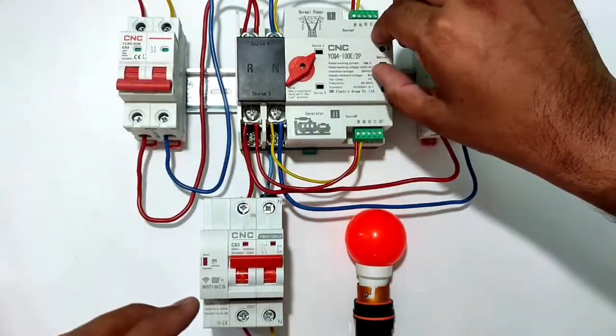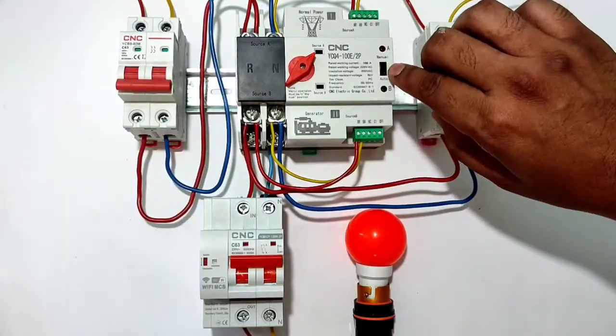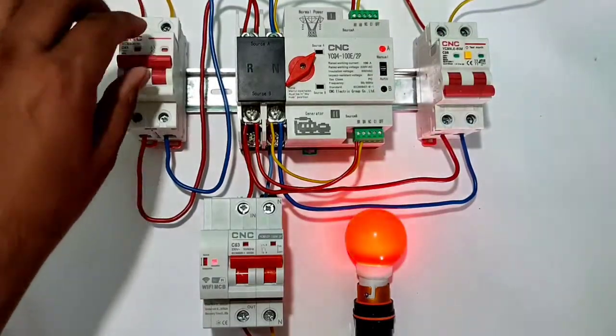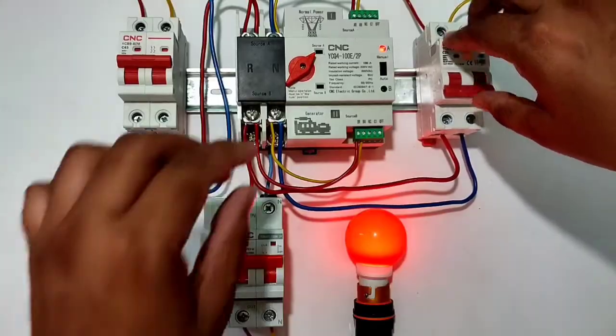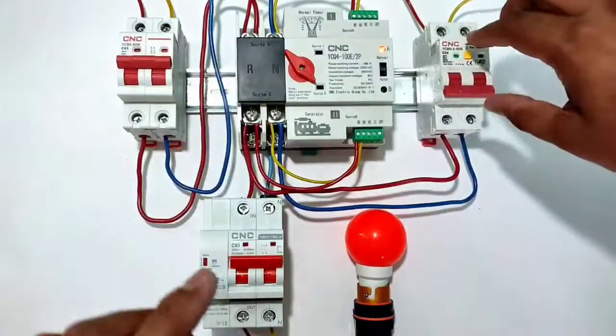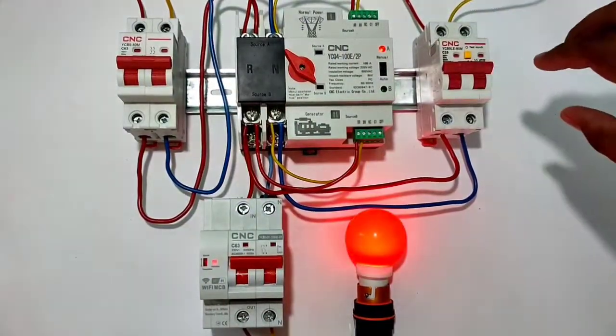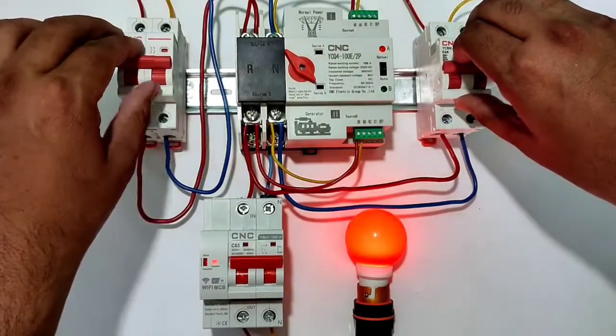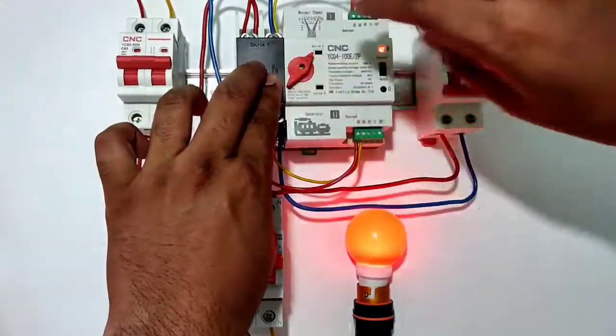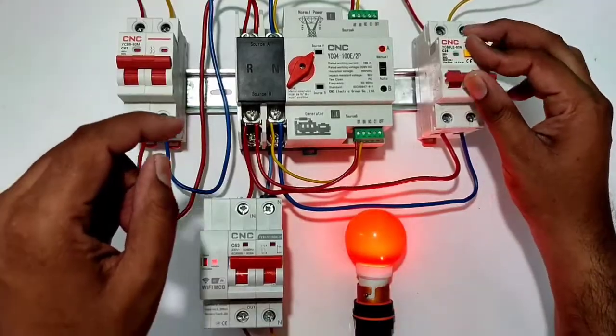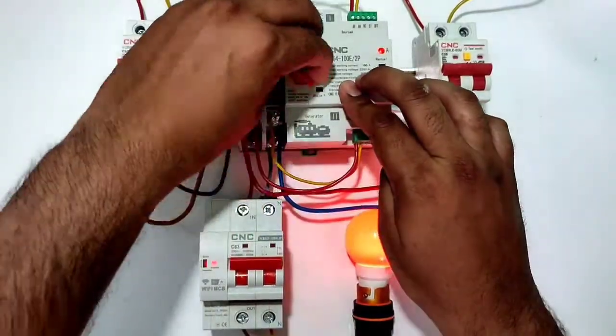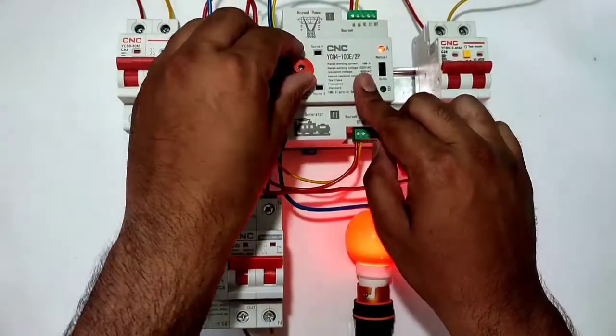It is simple. Now we select manual mode here, manually. Okay, we select manual mode. If you want to run your load on the main power supply, you can select it manually here. If you want to run your load on the generator power supply, you can select the generator power supply manually. So whichever supply you want your load to run on, you can select it here if you select manual mode.